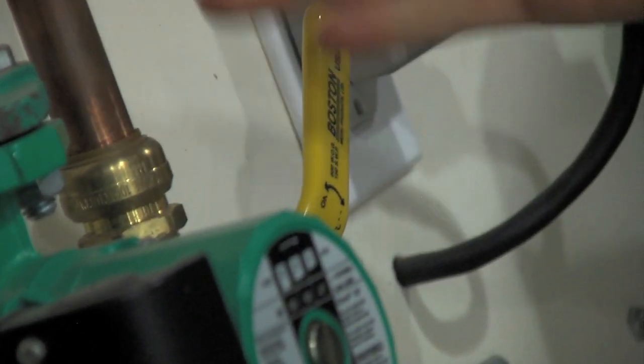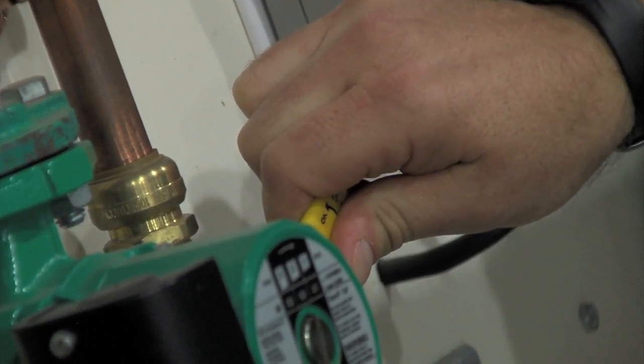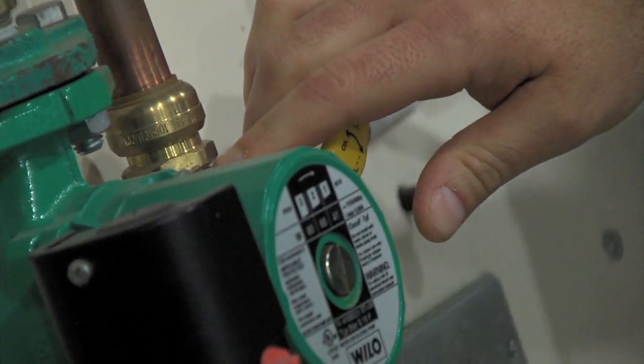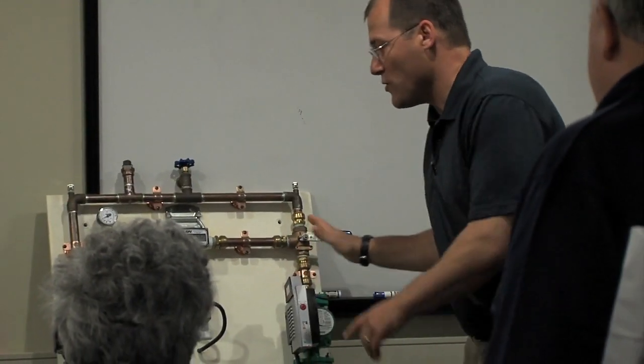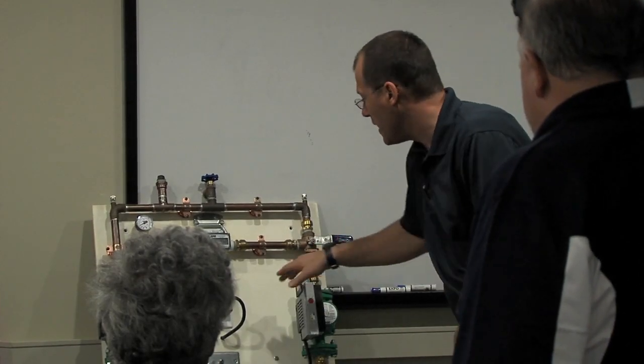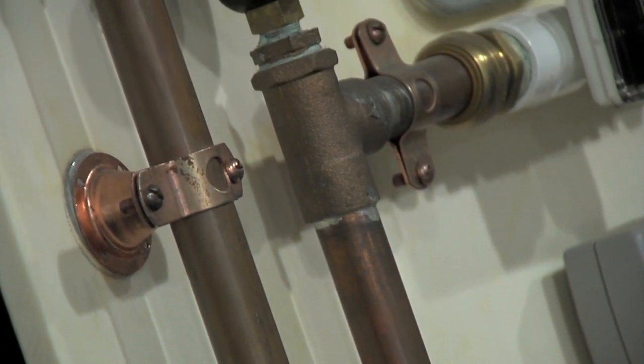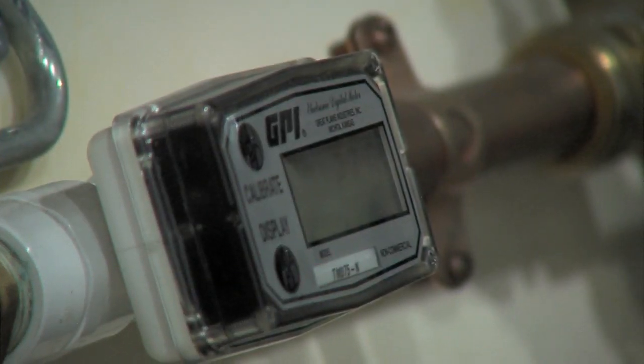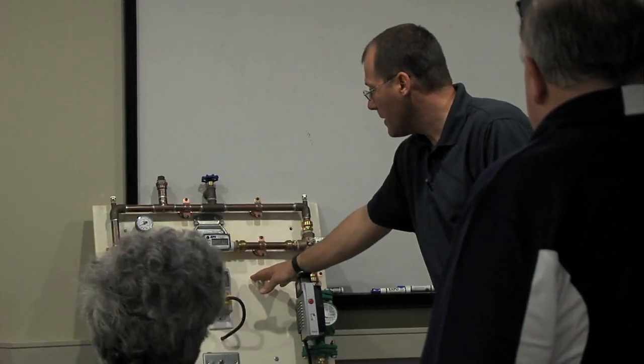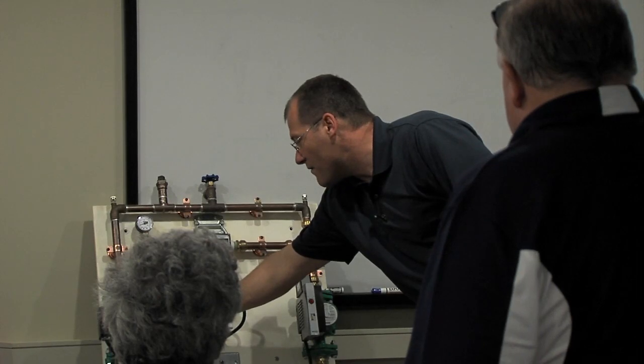Now, if I represent some restriction, which would be zone valves closing in the building, that was my worst day of the year with everything open. So let's cut the flow rate in half. You hear velocity noise because it's still trying to pump at its speed. One thing these new pumps get rid of is the need for a pressure bypass valve, and the velocity noise goes away. We're down at 4 gallons a minute. Let's get to about 3.5, which is half the zone valves closing, and we're at 55 watts. So we've affected the pump's watt consumption very little.